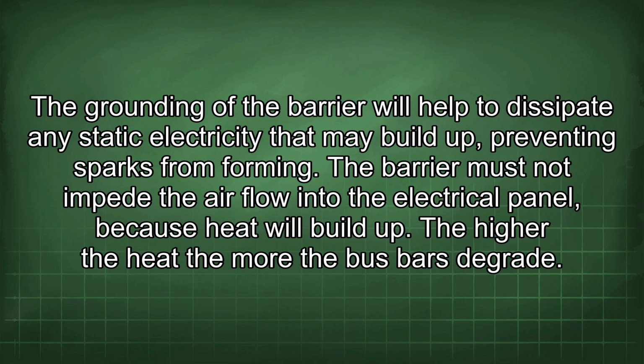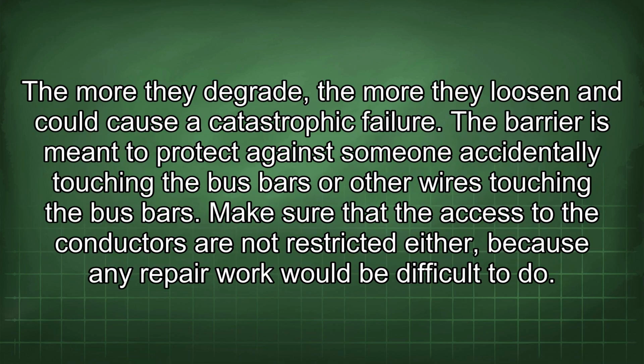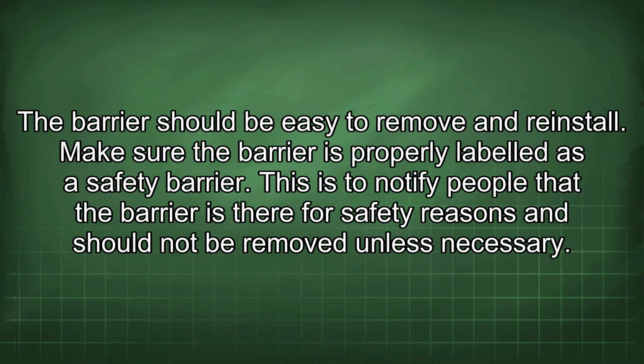The barrier must not impede the airflow into the electrical panel because heat will build up. The higher the heat, the more the bus bars degrade. The more they degrade, the more they loosen and could cause a catastrophic failure. The barrier is meant to protect against someone accidentally touching the bus bars or other wires touching the bus bars. Make sure that the access to the conductors is not restricted either, because any repair work would be difficult to do. The barrier should be easy to remove and reinstall.